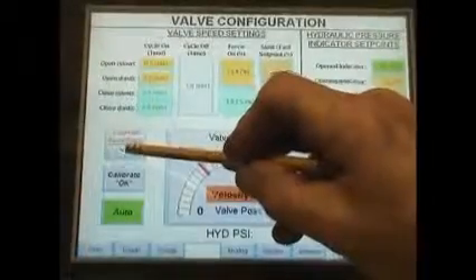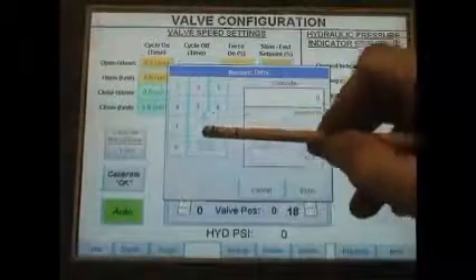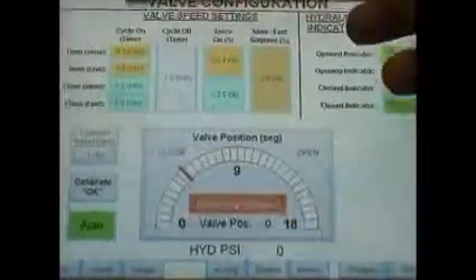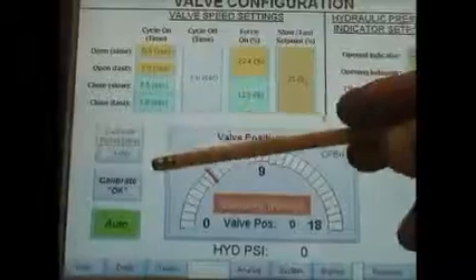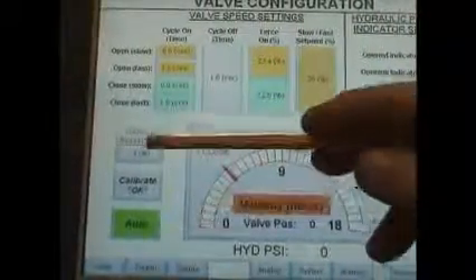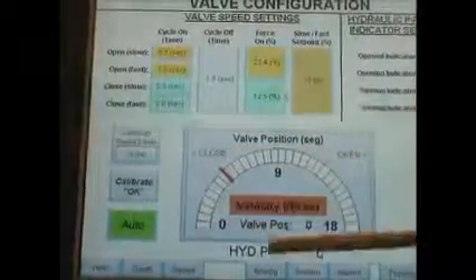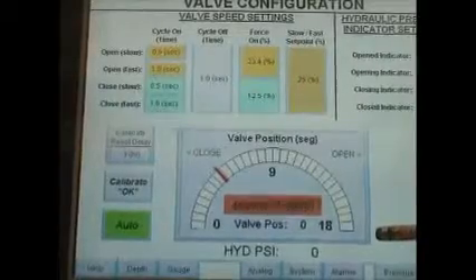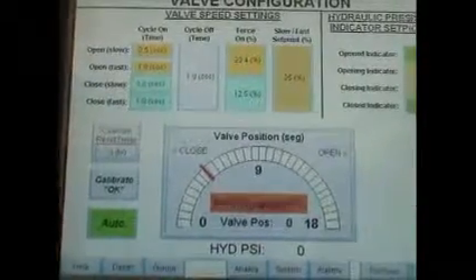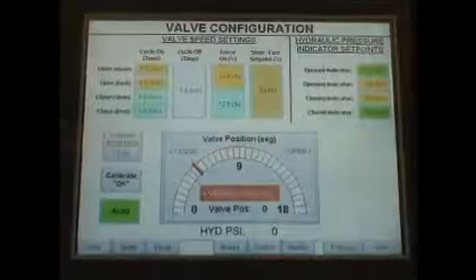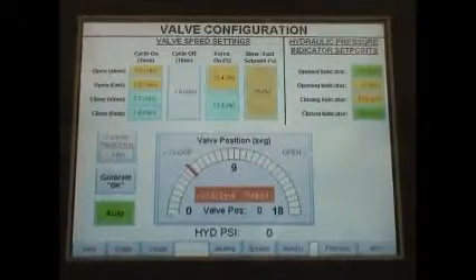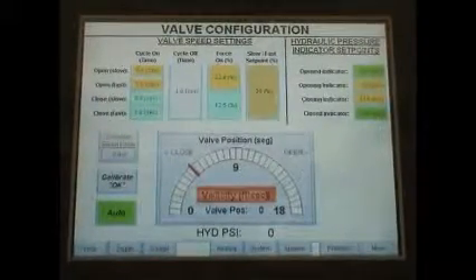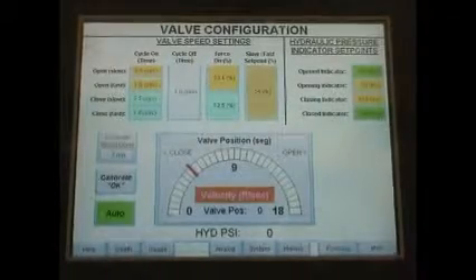Let's say we wanted to maybe calibrate once in 3 hours. So we can enter 3 in here. Now the computer is going to wait for 3 hours before it goes through the calibration process, unless your oil temperature has changed more than 30 degrees in one direction or the other. Then it will still calibrate based off of that temperature change.